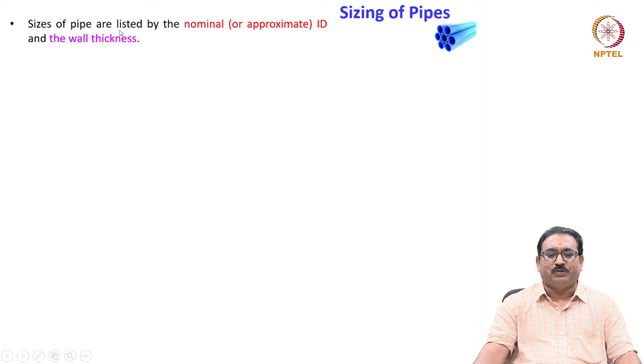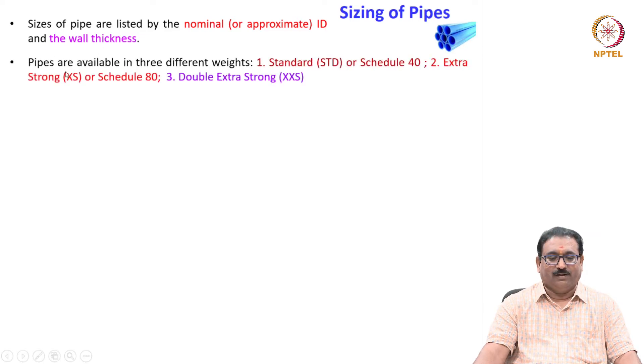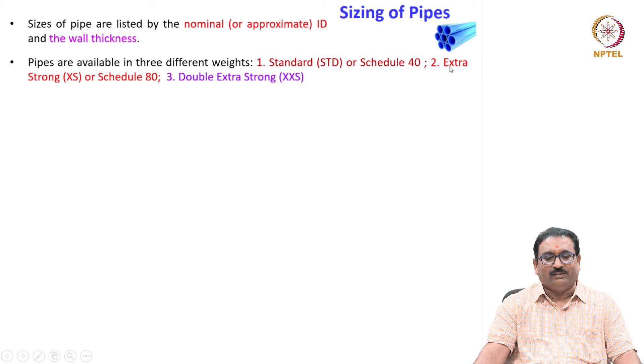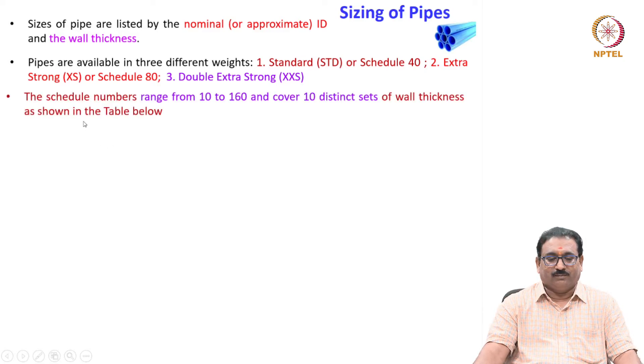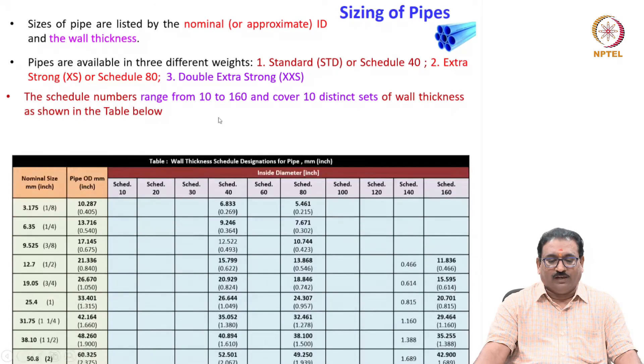Sizing of pipes is listed by the nominal or approximate inside diameter (ID) and the wall thickness. Pipes are available in three different weights: standard or Schedule 40; extra strong or Schedule 80; and double extra strong. The schedule numbers range from 10 to 160 and cover 10 distinct sets of wall thicknesses, as shown in the table.